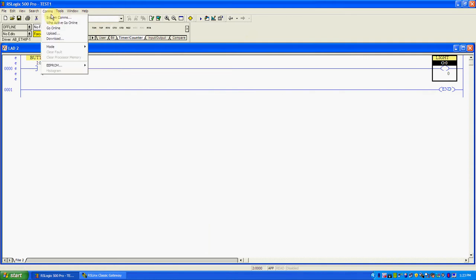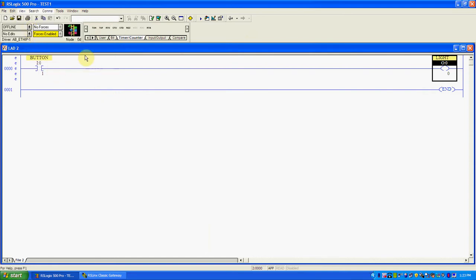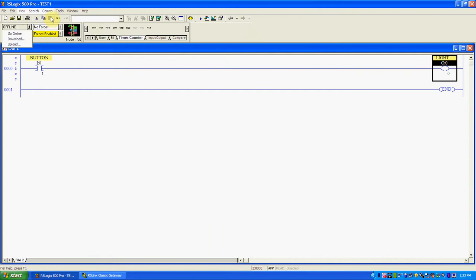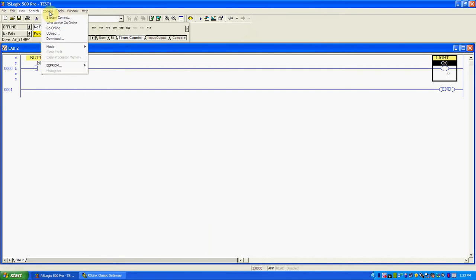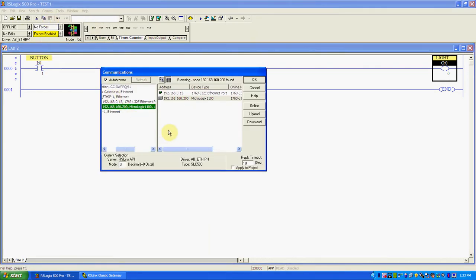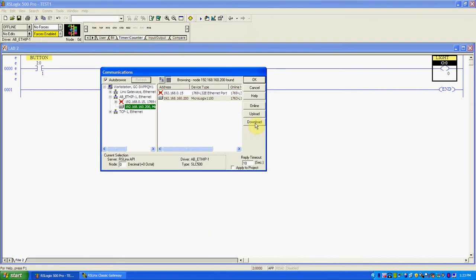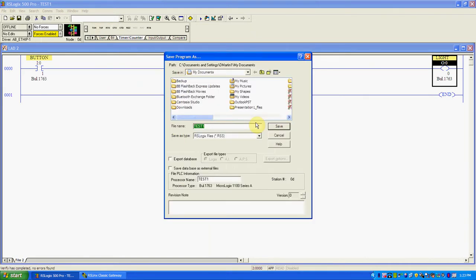Some of the stuff I'd like to cover is when you download — you can actually download two different ways. I want to send this now to the PLC, which is called download. The problem is this is going to download the way your network settings were set up when you built this offline program, and they may not be right — you may send it to the wrong place. In a factory that had 15 PLCs, downloading to the wrong place could mean you do a lot of damage or overwrite a program. The preferred way would be to use Comms, System Comms. In here you can actually see all the different things on our network. You can say we're using Ethernet, and there's my PLC, and I would like to download specifically to it.